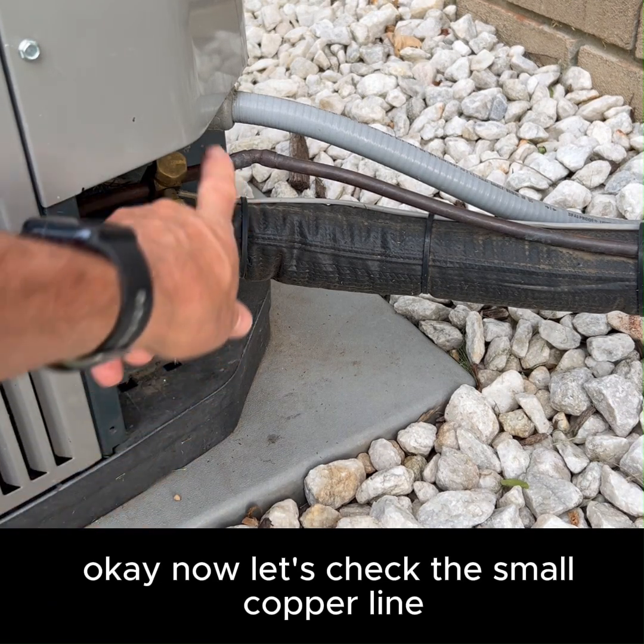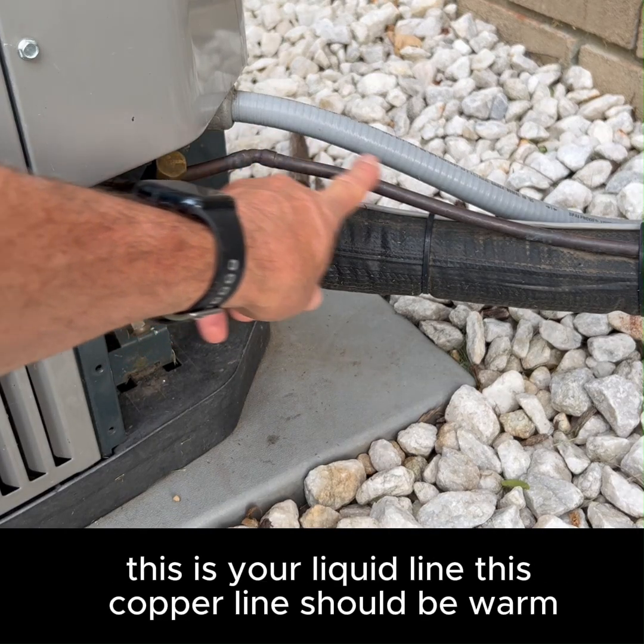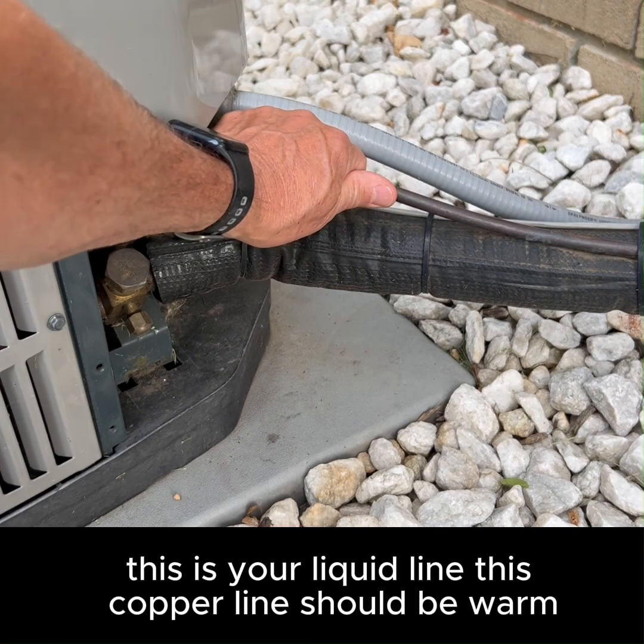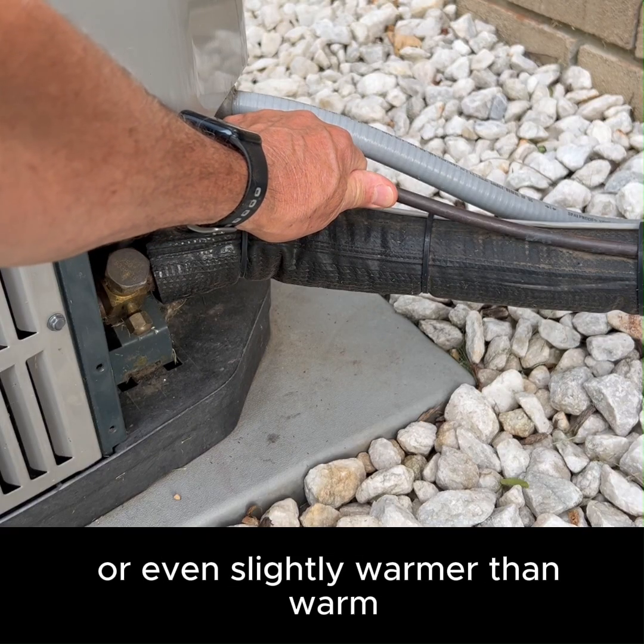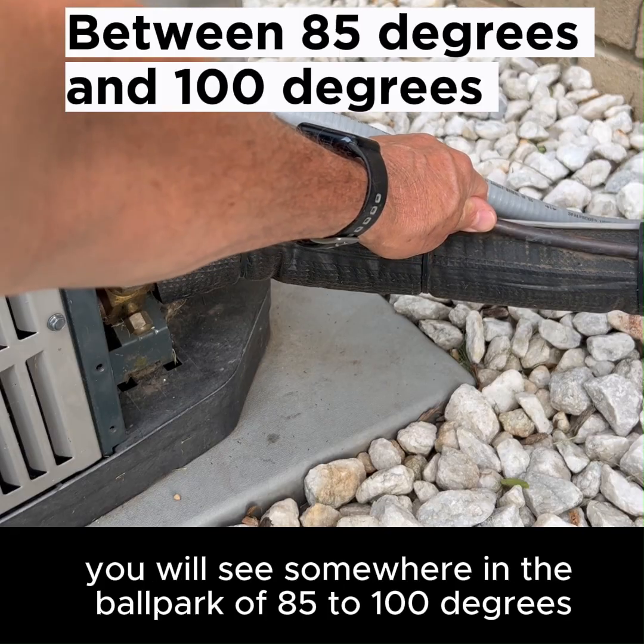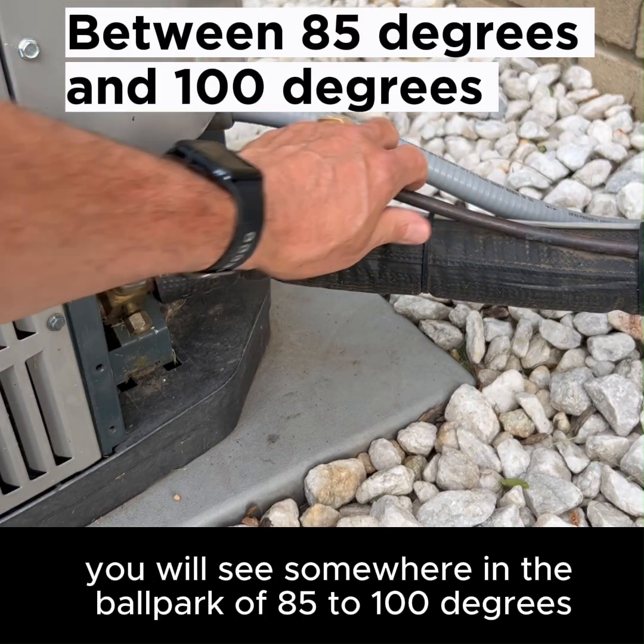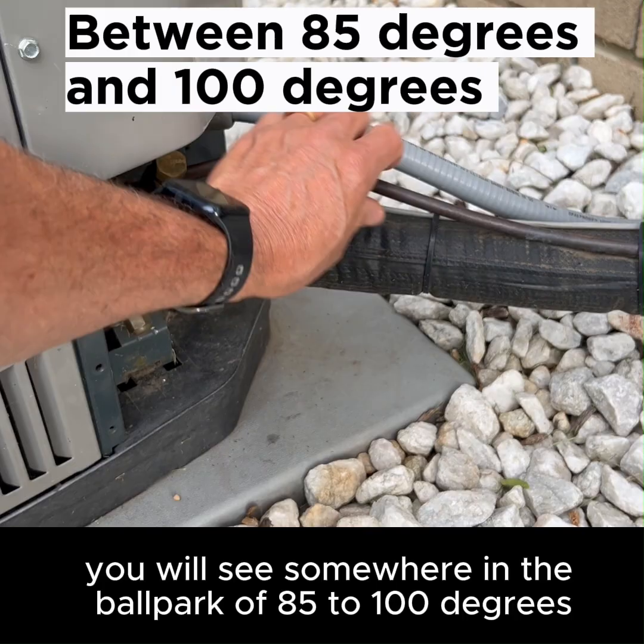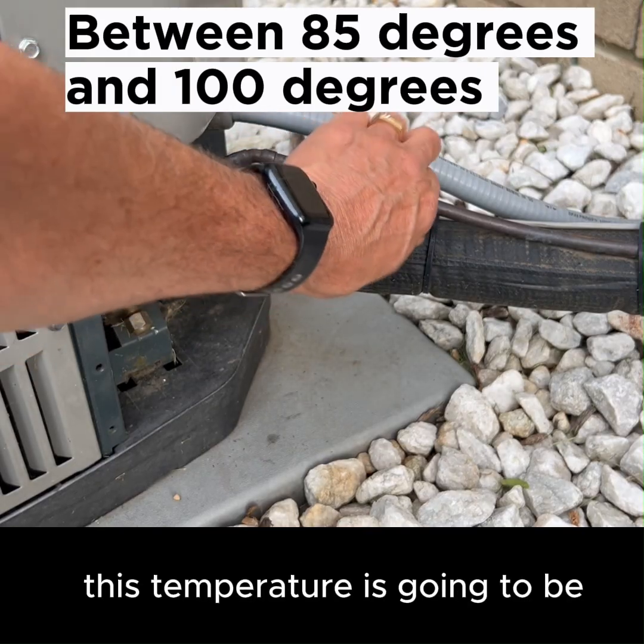Okay, now let's check the small copper line. This is your liquid line. This copper line should be warm or even slightly warmer than warm. Usually the temperature on the liquid line you will see somewhere in the ballpark of 85 to 100 degrees. Again, this temperature is going to be based on the ambient conditions in the house.